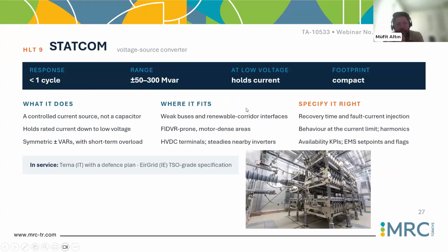So if we start with the latest and fastest one, STATCOM, the response time is less than one cycle, with a range depending on the installation. They are modular and flexible, so you can control them. You can integrate them with the renewable generation inside the systems. In Australia again, I know projects with both STATCOM battery and wind farms installed. Even for off-grid cases, you can use the STATCOM together with renewable generation plus synchronous condenser or other things, so it depends on the system.